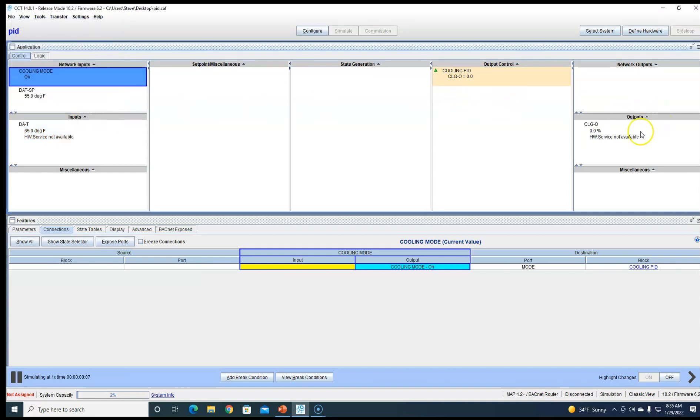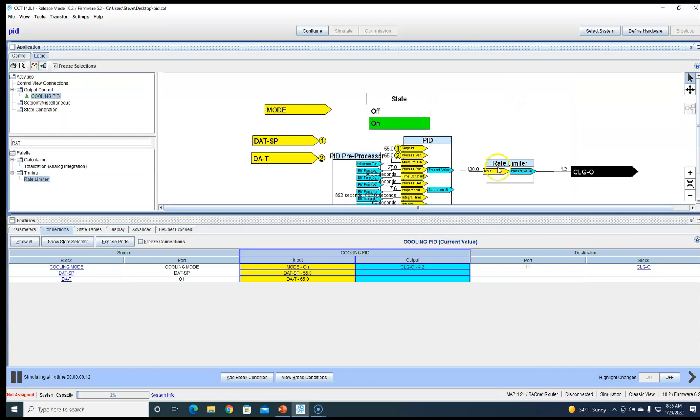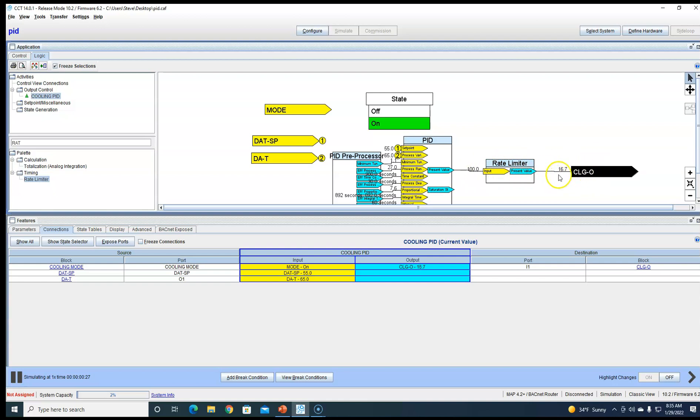Nothing's going to happen right now because our cooling mode is off, but whenever we turn our cooling mode on, we are going to get a very slow PID. View logic. So our PID's already putting the output of a hundred percent in here, but our rate limiter is limiting how fast that PID can go up.